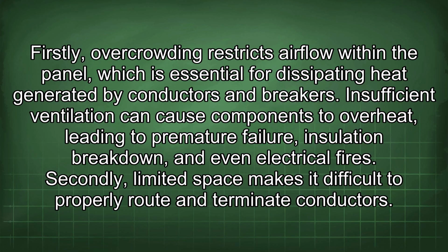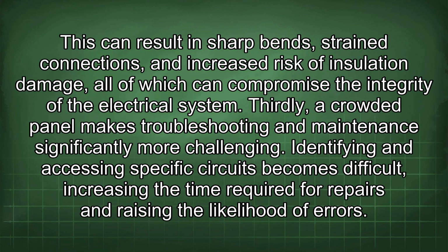Secondly, limited space makes it difficult to properly route and terminate conductors. This can result in sharp bends, strained connections, and increased risk of insulation damage, all of which can compromise the integrity of the electrical system. Thirdly, a crowded panel makes troubleshooting and maintenance significantly more challenging. Identifying and accessing specific circuits becomes difficult, increasing the time required for repairs and raising the likelihood of errors.